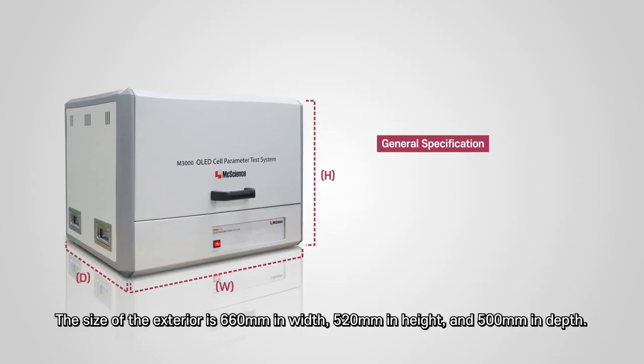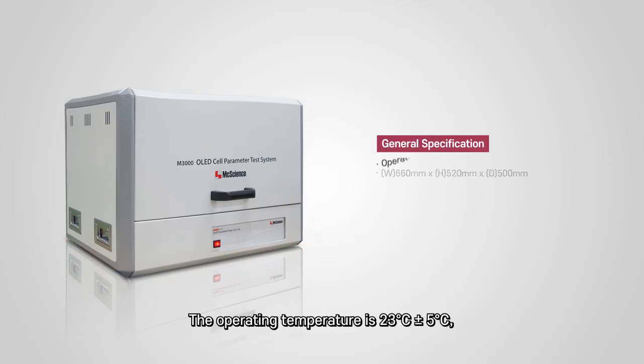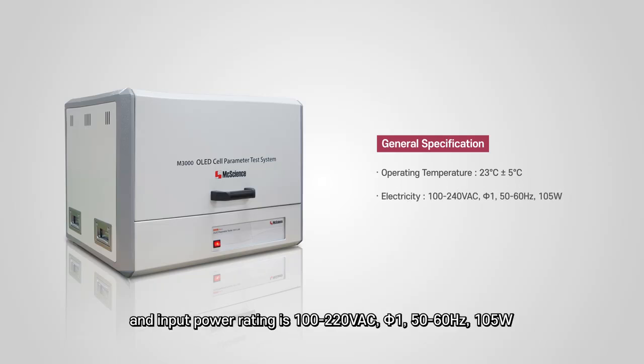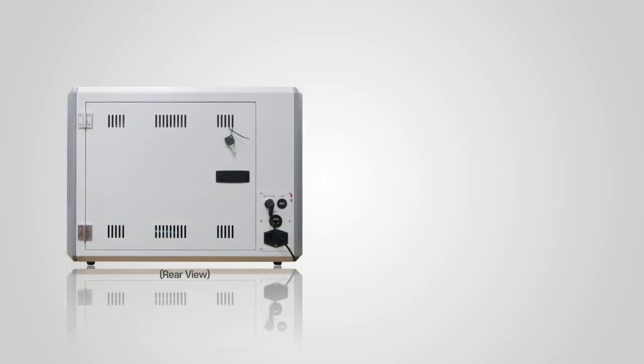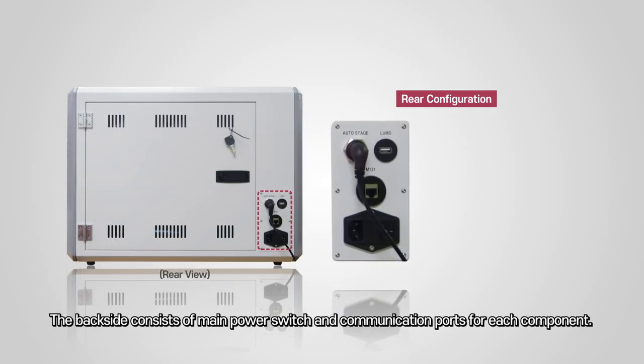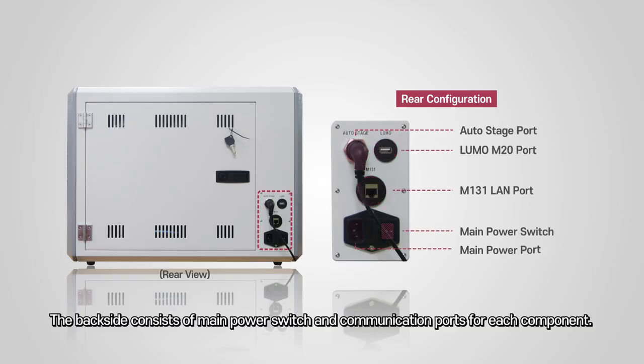The size of the exterior is 660 mm in width, 520 mm in height, and 500 mm in depth. The operating temperature is 23 degrees Celsius plus or minus 5 degrees, and the input power rating is 100 to 220 volt AC, single phase, 50 to 60 Hz, 105 watts. The backside consists of the main power switch and communication port for each component.